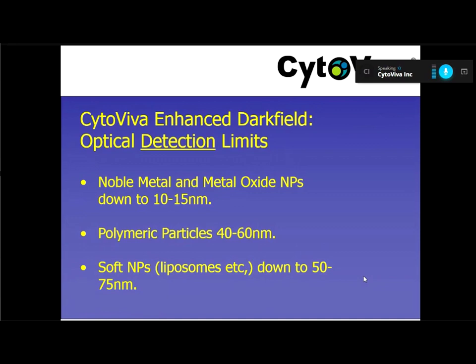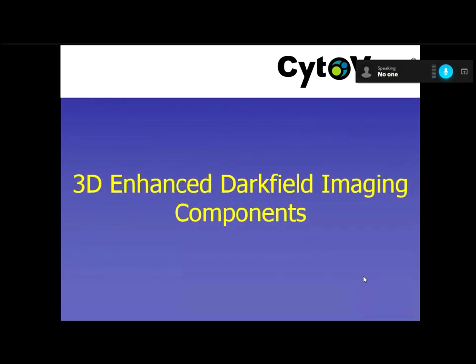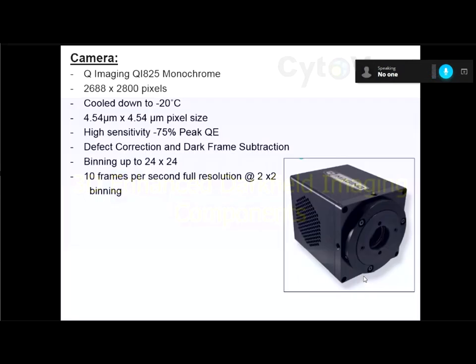In practical terms: for noble metals and metal oxide nanoparticles, you can detect scatter of light off particles down to about 10 to 15 nanometers. For polymeric particles, it goes down to between 40 and 60 nanometers. And for soft particles like liposomes and lipid particles, down to about 50 to 75 nanometers.